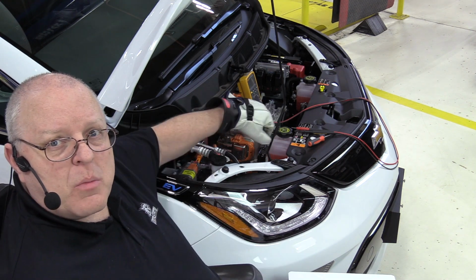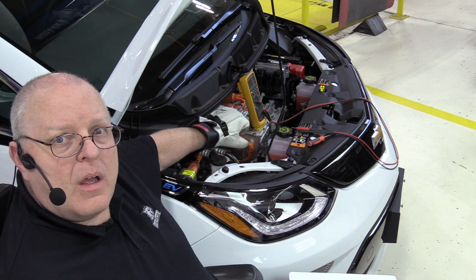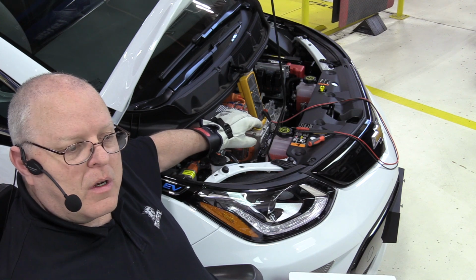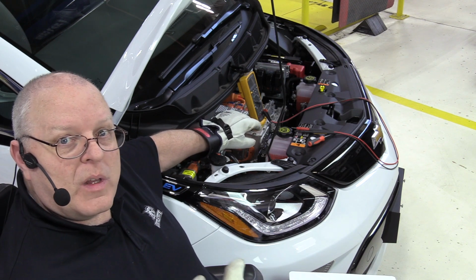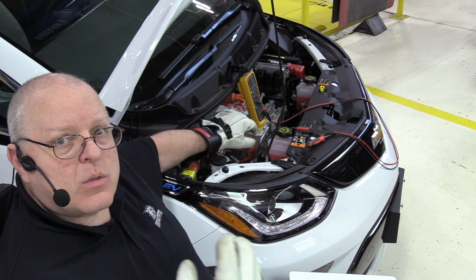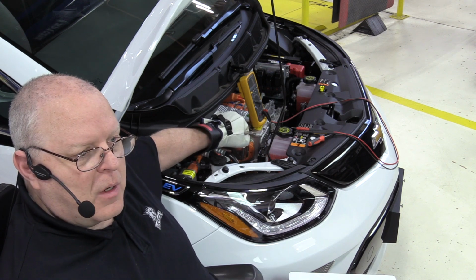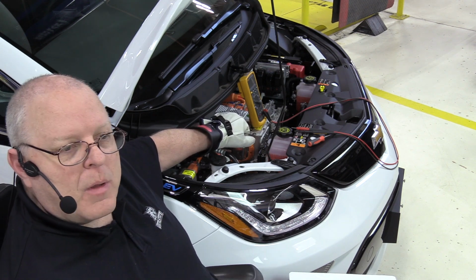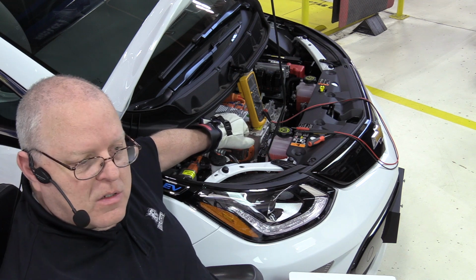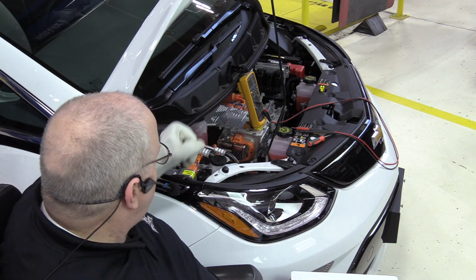And when we take a measurement on this electrical connector here, we do not want to see high voltage on it, but we want to make sure that there really is no high voltage, and that's why we make sure our meter is working properly. A meter that isn't working properly may not show you high voltage when there actually is high voltage. So our meter is good.